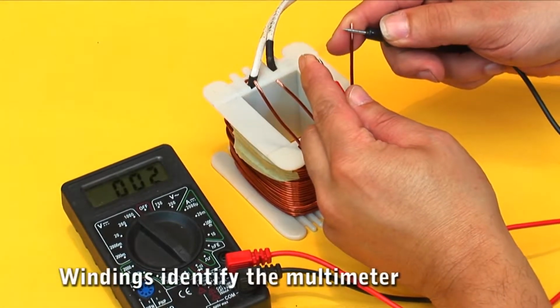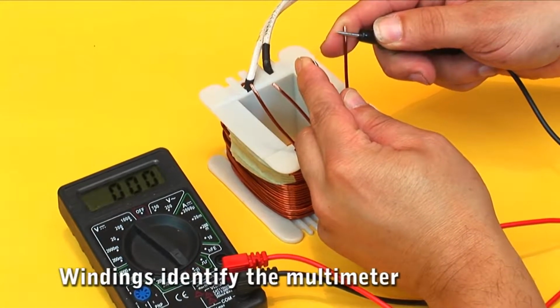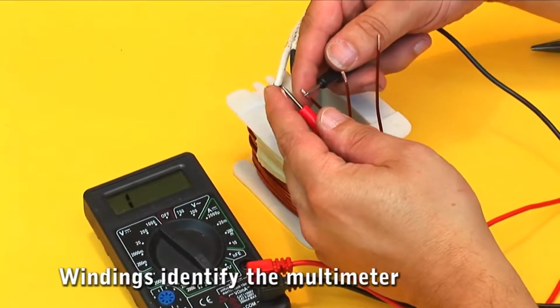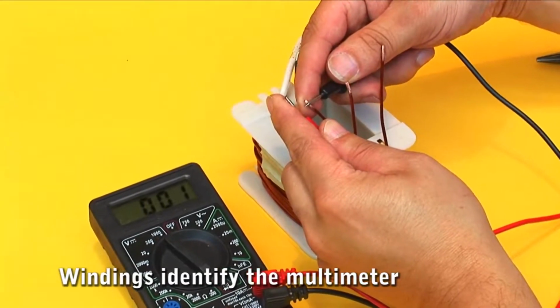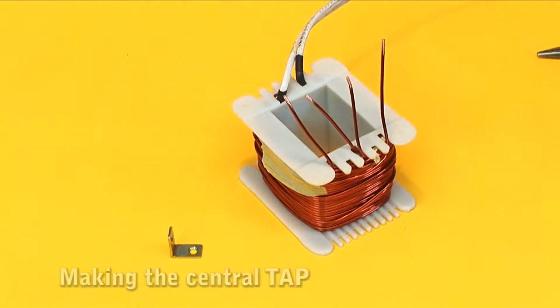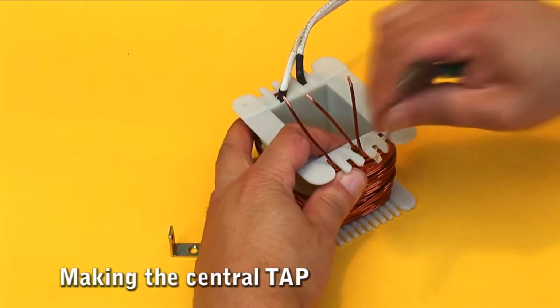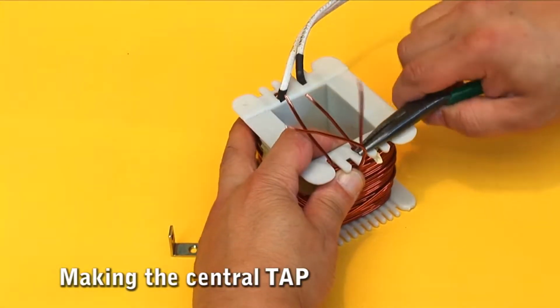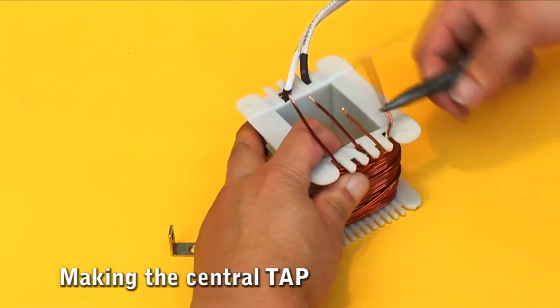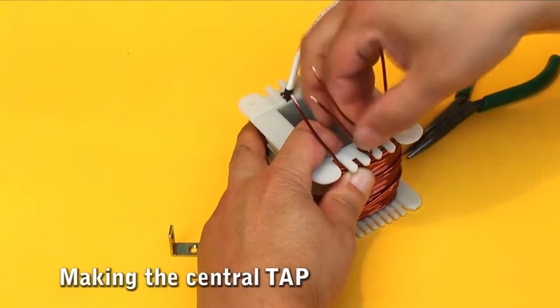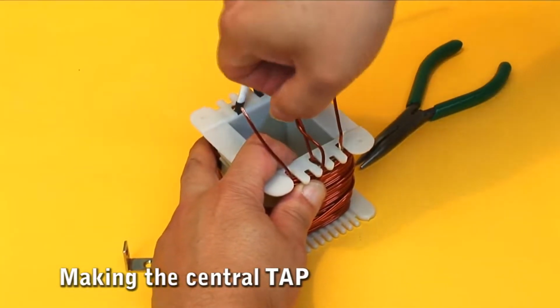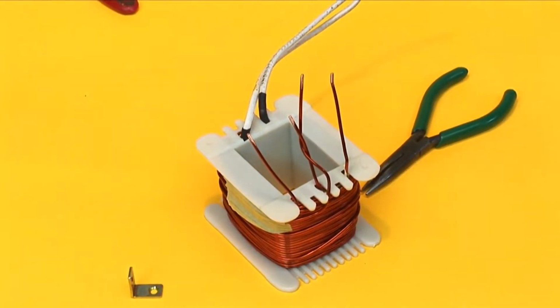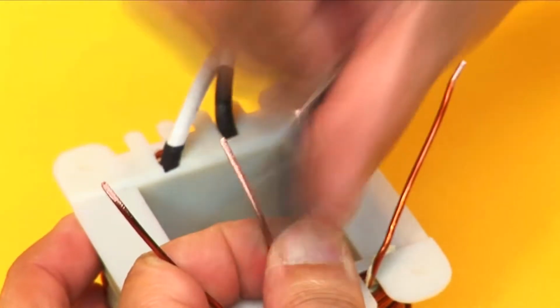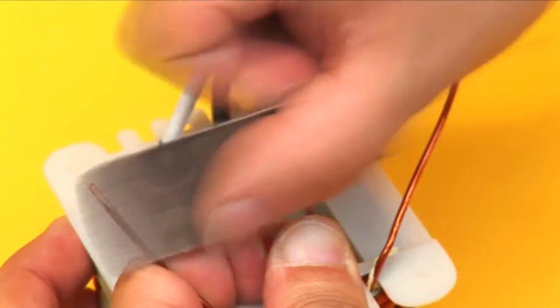Detecting the central tap of the transformer. We must identify the ends of the windings, measuring continuity with a multimeter. It is necessary to join the leading end of one winding with the tail of the other winding. The starting point of one secondary winding must join the tip end of the other secondary winding, thus forming the central tap. In order to weld the central tap point, remember to sand the pieces of wire so that there is adhesion of the solder and good conduction.